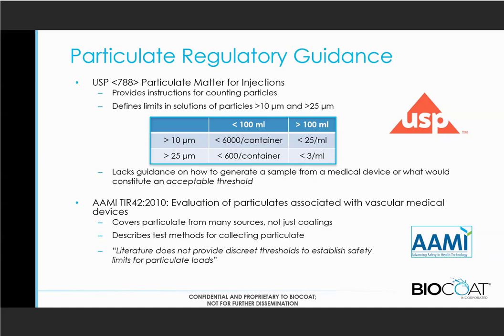Another standard is from AAMI, another technical report, evaluation of particulates associated with vascular medical devices. And as I had mentioned, it covers particulates from many sources, not just the coating, so that entire procedure. It does give some description on how to collect particulates, but explicitly states that the literature does not provide discrete thresholds to establish safety limits for particulate loads.